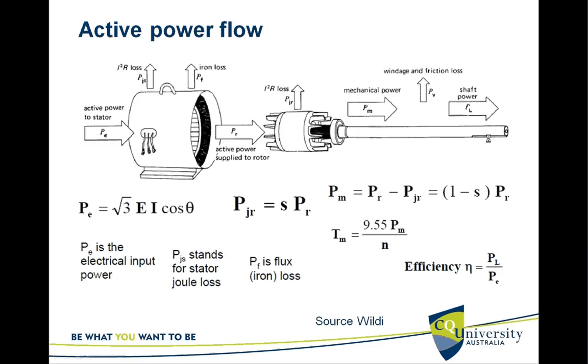Looking at the equations: the electrical input power Pe = √3 × E × I × cos θ. PJS stands for stator joule loss — that is the stator power loss. PF is the flux or iron loss.